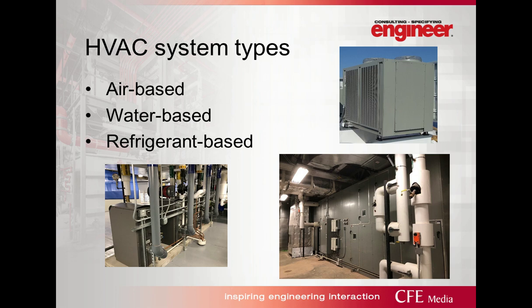Another basic air-based equipment option is fan coils or furnaces with air-cooled condensing units. These systems at their smallest size might be what you have in your house, and the units go up to a few tons to serve retail spaces or office spaces. Fan coils typically max out at about 1,500 CFM before they are called air-handling units, but that's nomenclature that varies by manufacturer, region of the country, and engineer. Typically, this changeover is around the 3 to 4 ton mark.